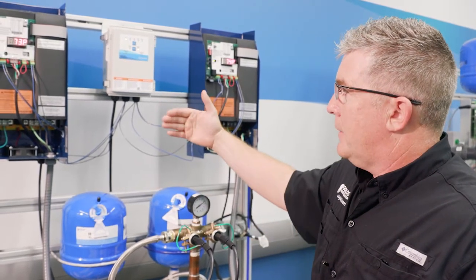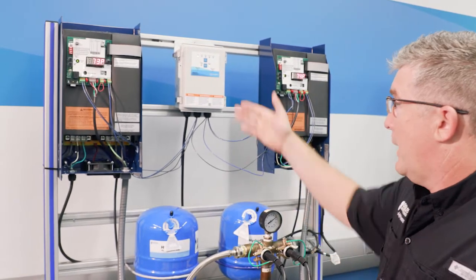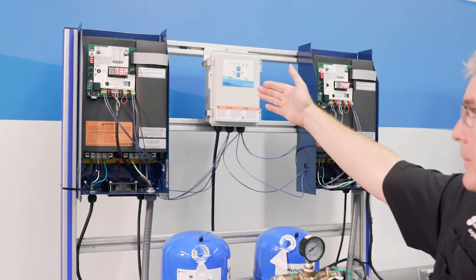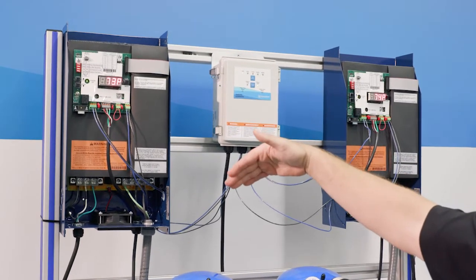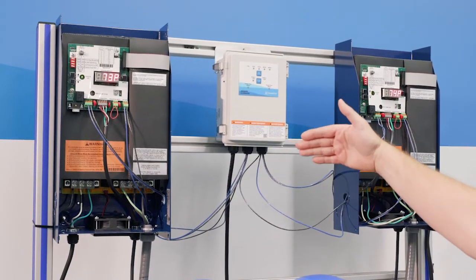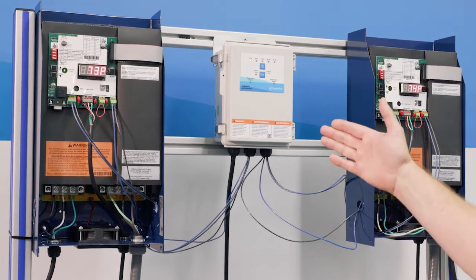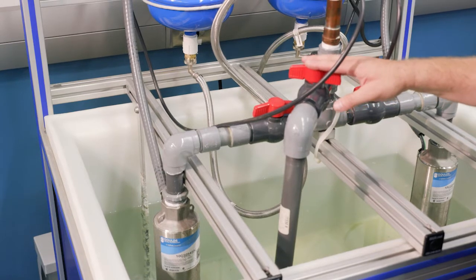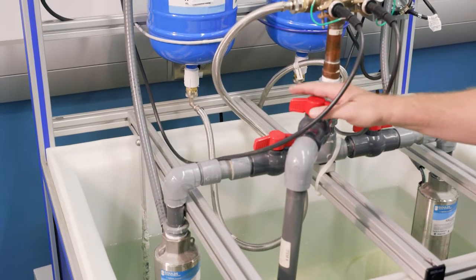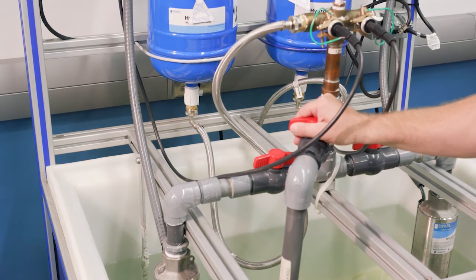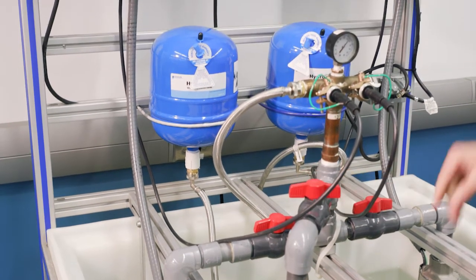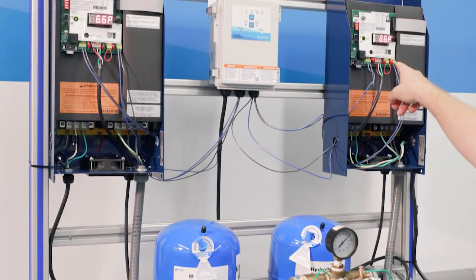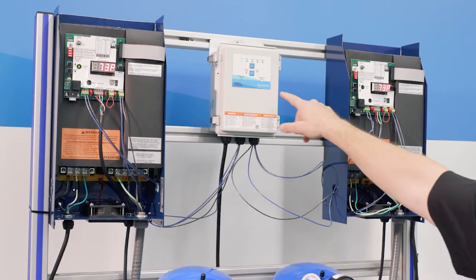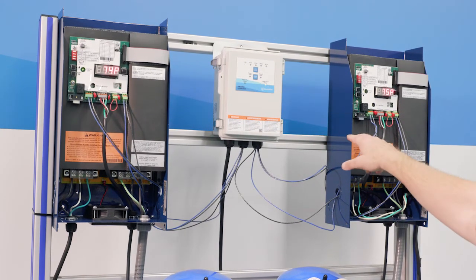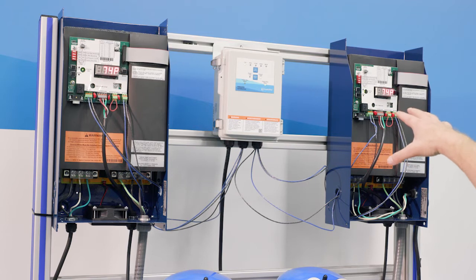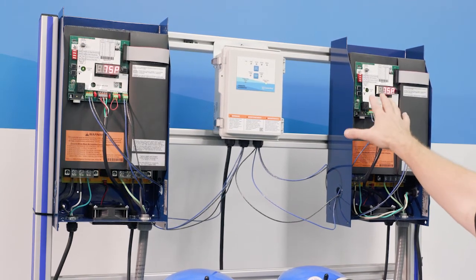So let's take a look and observe how it works. Now, we're not going to view the alternation because that's based on 1 hour of runtime. But we are going to see the lead lag operation. Let's take a look at our operation running. So I'm going to give it some demand. I'm going to open up the discharge valve. So I can see that pump 2, that's our lead, is running right now. All right, so I'm maintaining my lead pressure, which is SP2.